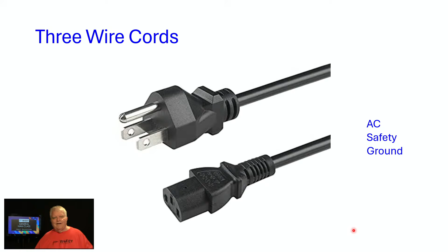Use cable and wire that's rated for the expected current load. The current rating for wire is something called ampacity, the capacity for amperage. And the two most common sizes for house wiring are number 12 American wire gauge, and that's suitable for 20 amp circuits, and number 14 American wire gauge, which is suitable for 15 amp circuits.